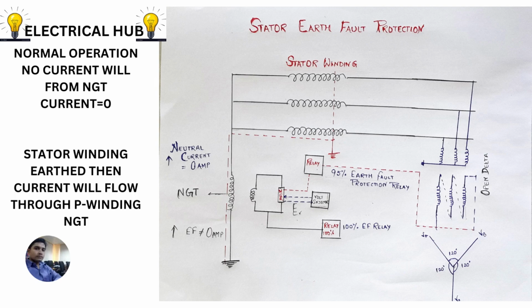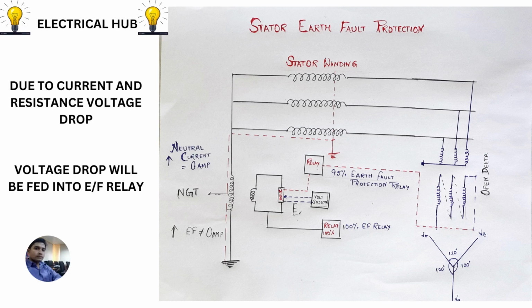But if any of the stator winding is earthed, then a huge current will flow through the neutral line, and it will induce current in the secondary of the NGT, where a load resistor NGR is connected. So, as the secondary of the NGT gets induced with current, it will also flow through the NGR, the neutral grounding resistor, which is connected along with the NGT.